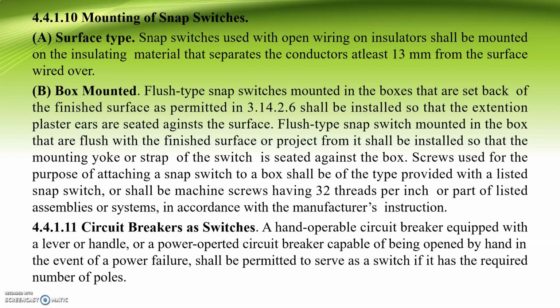So chapter 4.4.1.11, circuit breakers as switches. So a hand-operable circuit breaker equipped with a lever or handle, or a power-operated circuit breaker capable of being opened by hand in the event of a power failure, shall be permitted to serve as a switch if it has the required number of poles.